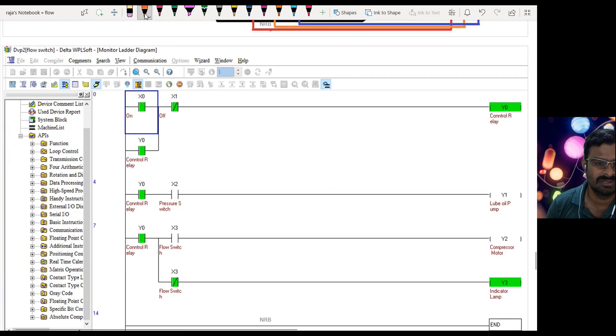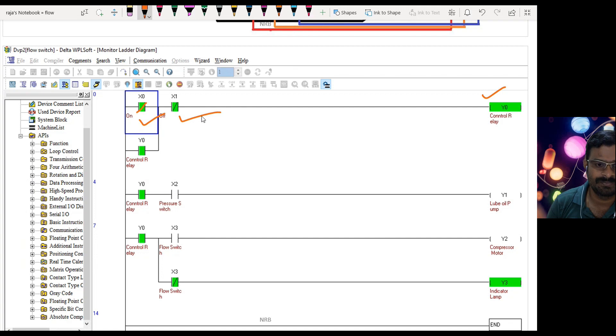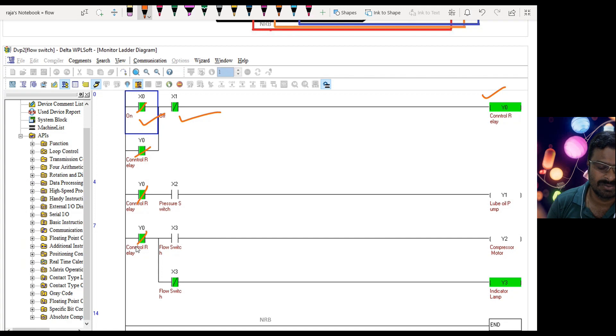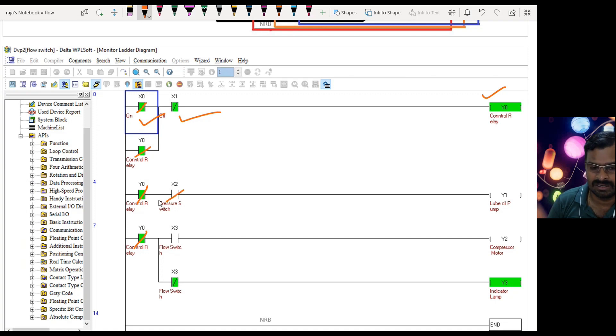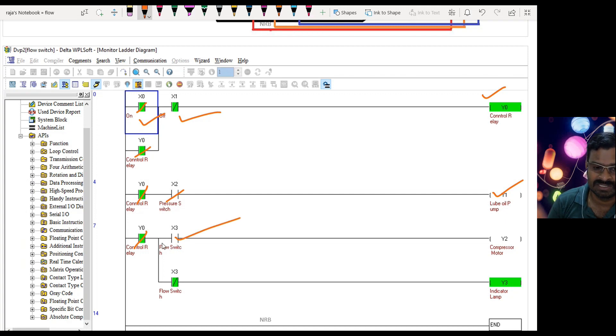The ladder logic code is also simple. We have an on switch, off switch, and control relay. When the on switch is closed, the Y0 coil energizes — the control relay gets energized and closes the Y0 contact wherever it appears. It then waits for the pressure switch to give a signal. When the pressure switch is at its set pressure, the lube oil pump is enabled, and when the pump runs, the flow switch detects the flow.